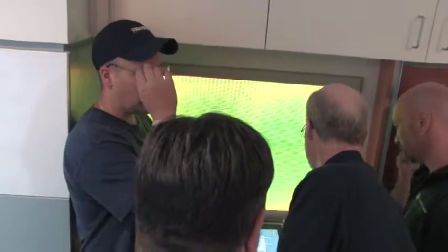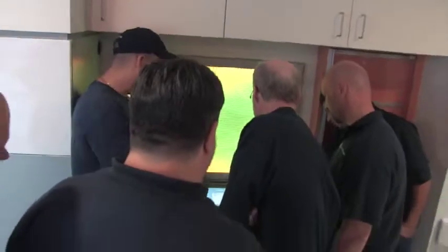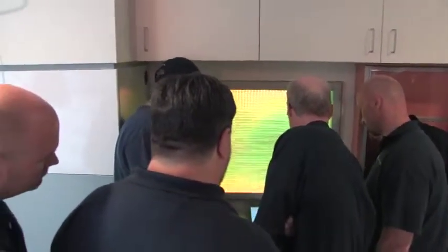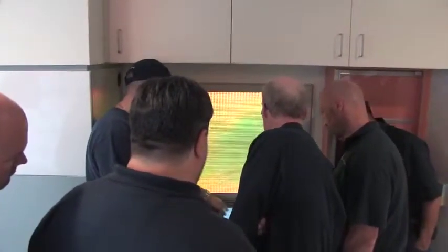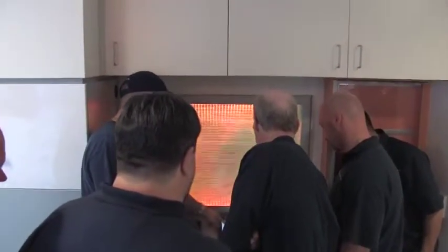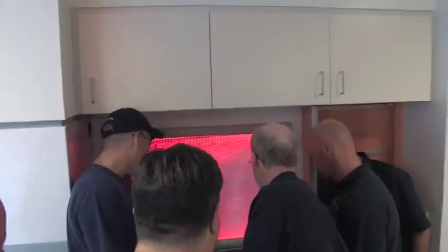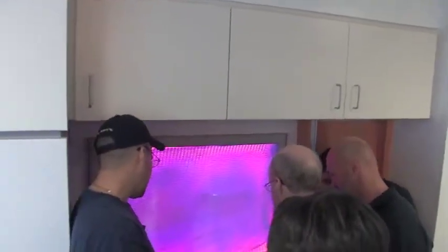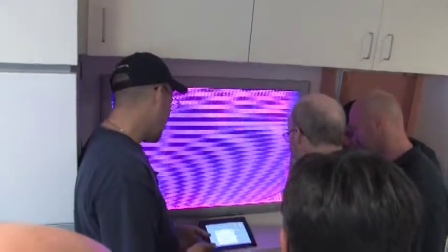But pretty much, these rooms will have humidity in them. You'll have air changes. And they'll have a differential, a DP across it, so you'll get an alarm if the pressure in the room goes positive or negative, depending what type of room it is. Again, you'll have your set points, your min maxes, your radiant panel. That stuff hasn't been done yet because that was something that we were going to end up changing in the end as far as the program change.